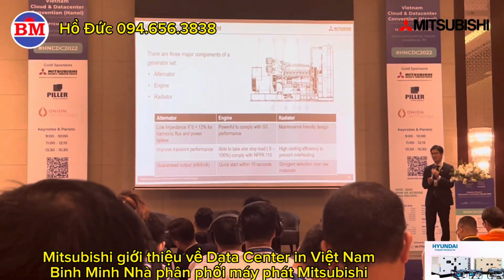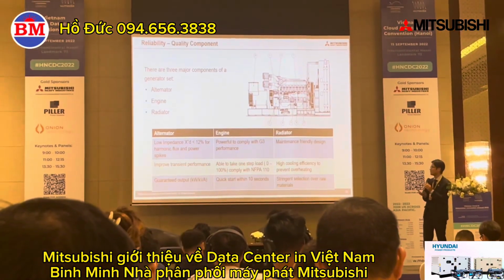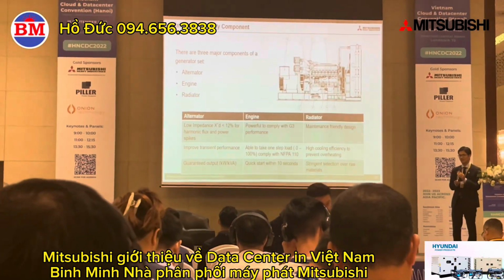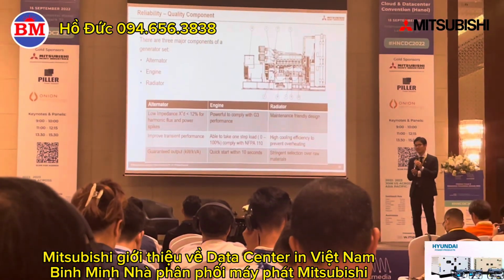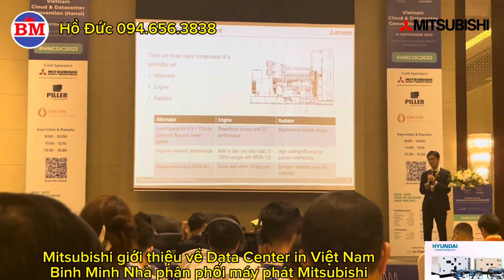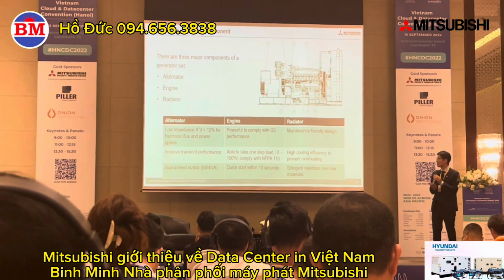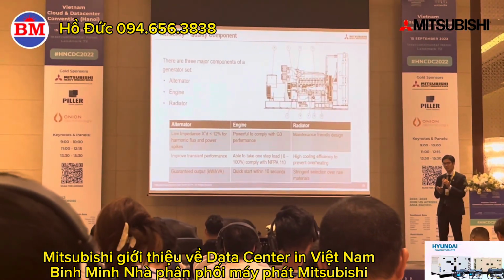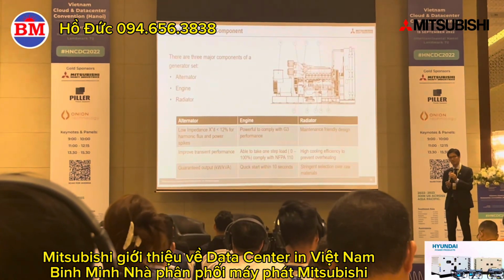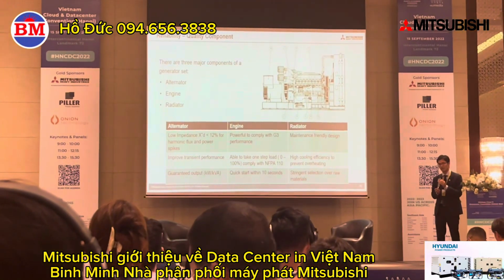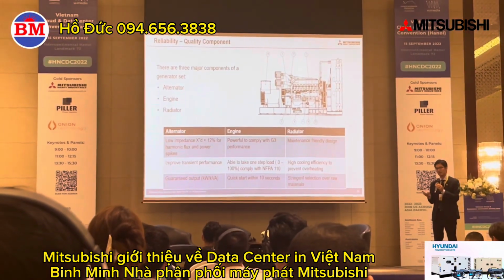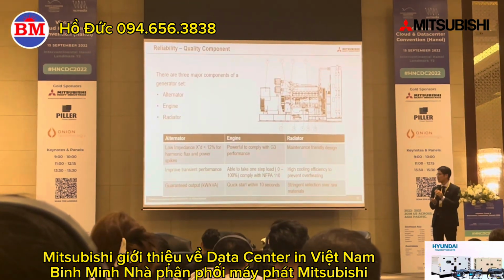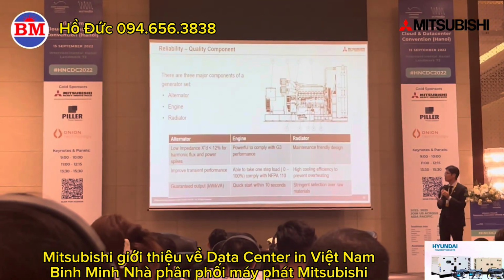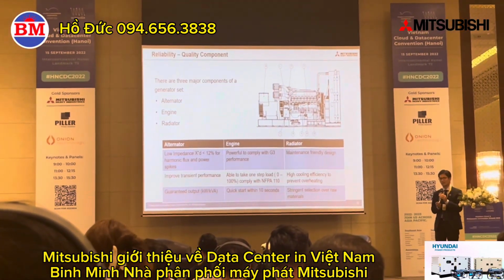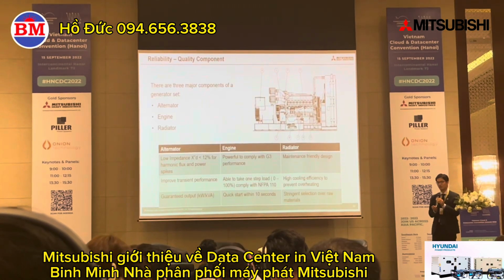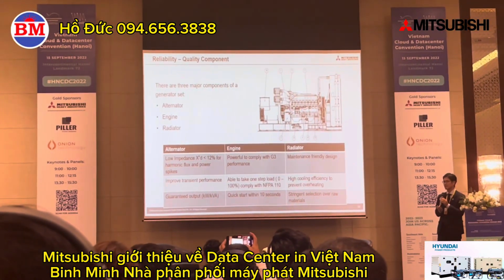Looking at the generator set, there are three major components: alternator, engine, and radiator. The alternator is a key component affecting electricity quality. For data centers, there is much more digital equipment compared to conventional use, so harmonic flux will be higher. To reduce this harmonic flux, you need to use a low impedance alternator. This kind of selection is important for a data center generator set.